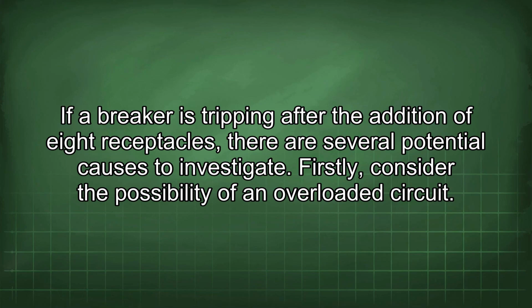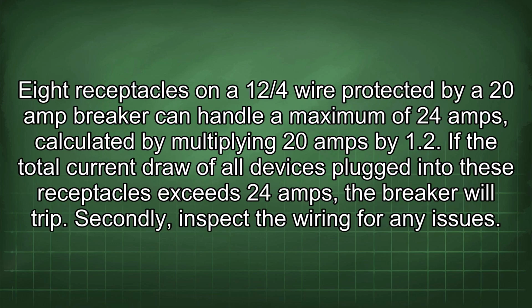If a breaker is tripping after the addition of 8 receptacles, there are several potential causes to investigate. Firstly, consider the possibility of an overloaded circuit. 8 receptacles on a 12/4 wire protected by a 20-amp breaker can handle a maximum of 24 amps, calculated by multiplying 20 amps by 1.2. If the total current draw of all devices plugged into these receptacles exceeds 24 amps, the breaker will trip.